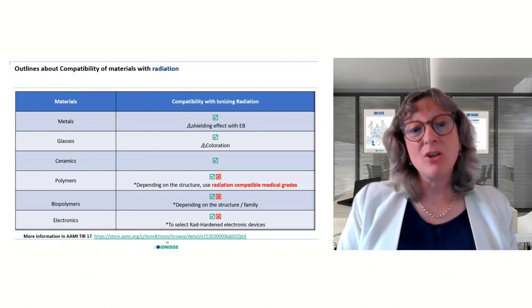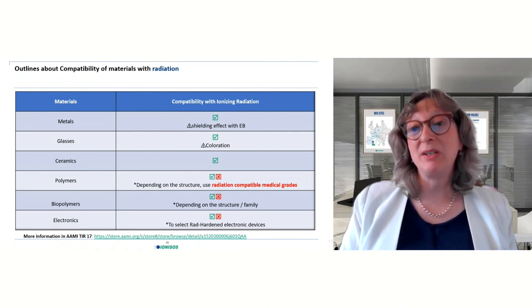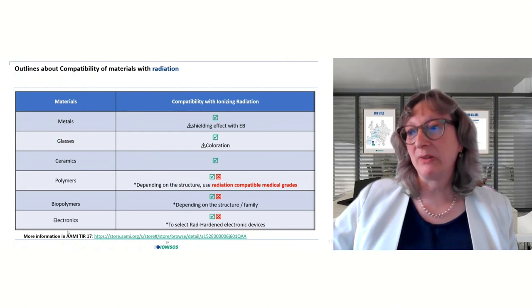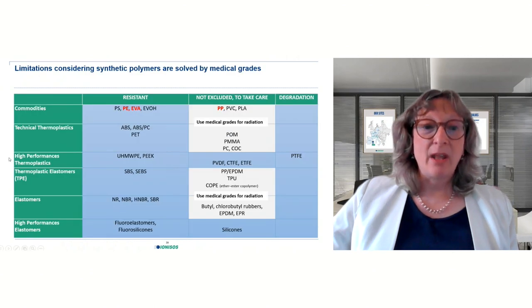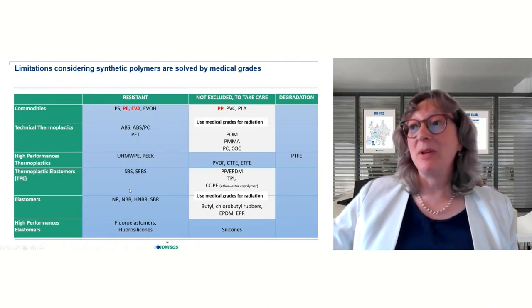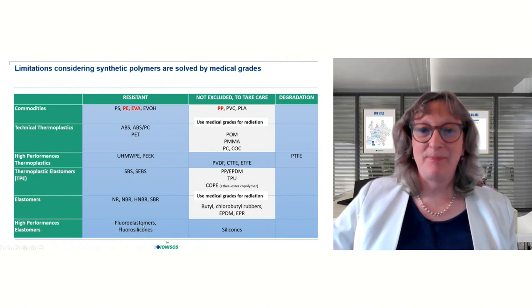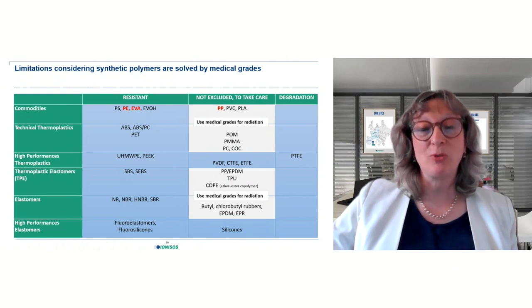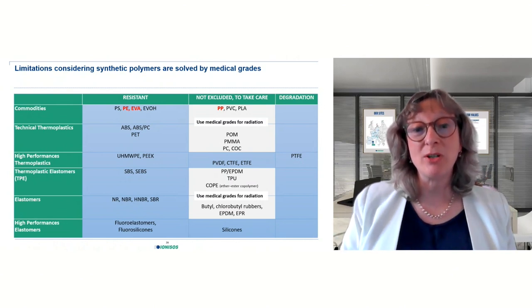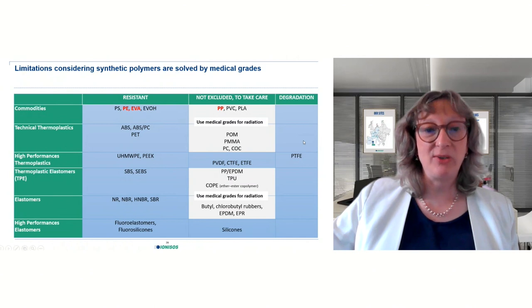In real life, materials modification with radiation is typical of polymers and biopolymers, not metals or glasses or ceramics. But half of the polymers used in medical applications are not impacted. And for the second half, fortunately, plastic suppliers have succeeded to overcome the radical rearrangements and develop radiation-compatible medical grades.